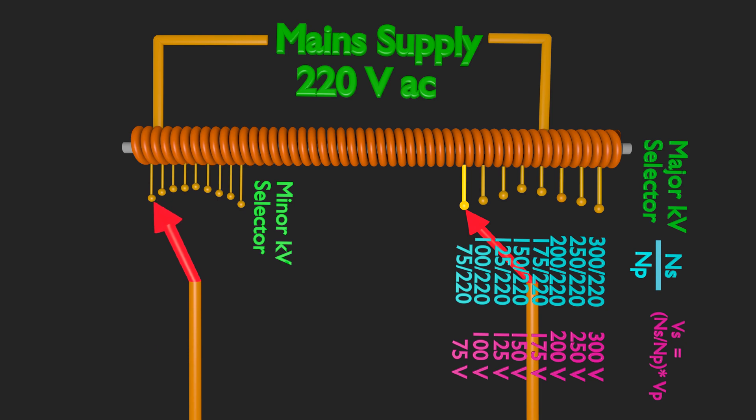Let's assume that the turn ratio for last tapping of minor selector is such that it produces a voltage of 1 volt across secondary. The final voltage across secondary will be voltage due to major selector plus voltage due to minor selector. That is in our current situation, 75 volts due to major and 1 volt due to minor selector, both adding to a voltage of 76 volts.